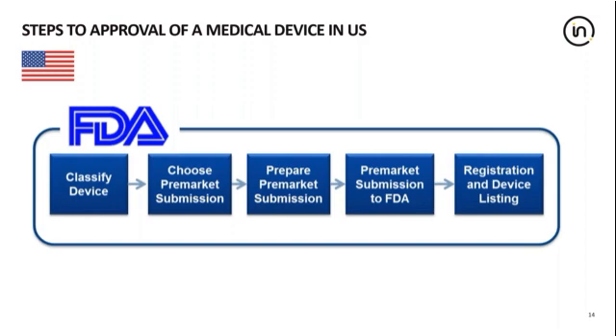A submission, known as a 510K, is a pre-market submission which is made to the FDA. And the purpose of this is to demonstrate that the device is as safe and effective as other similar products which are already on the market. And the device should be compared to one or other devices which are there, and there should be evidence to substantiate that it is equivalent to other products on the market.